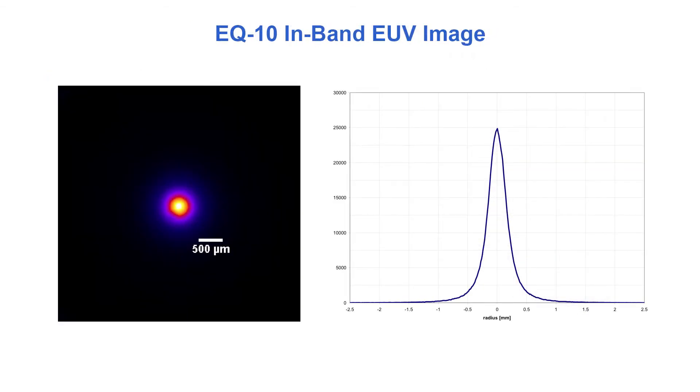It has a typical EUV plasma size of around 500 microns. This plasma size and its position are very stable, varying by only a few microns pulse to pulse. The pulse frequency of up to 2.5 kHz can be set by the user according to their application.